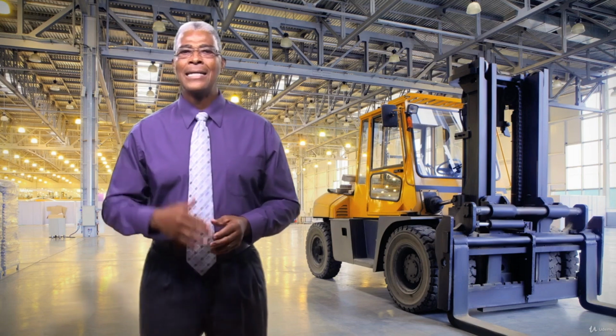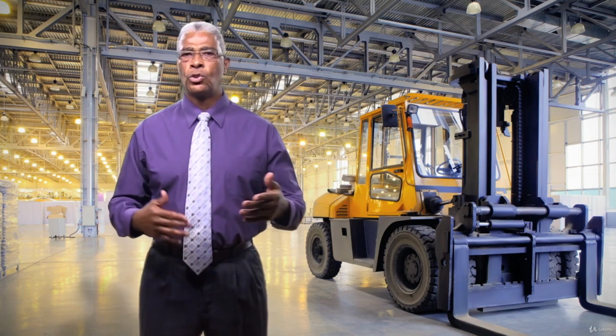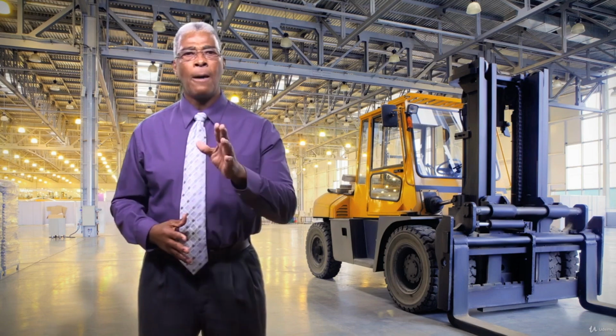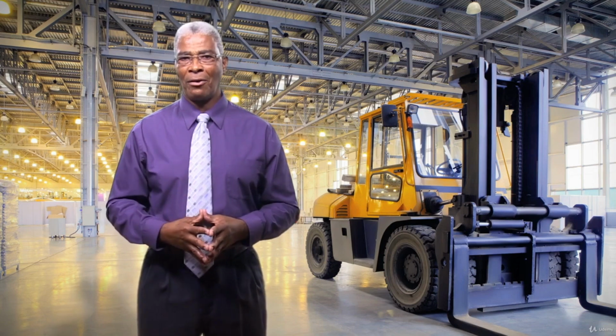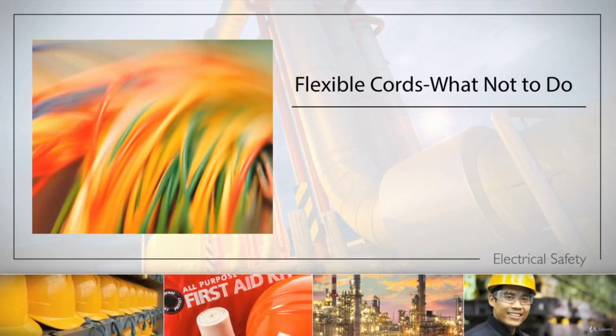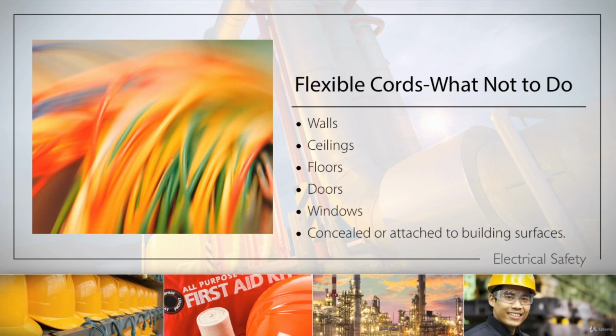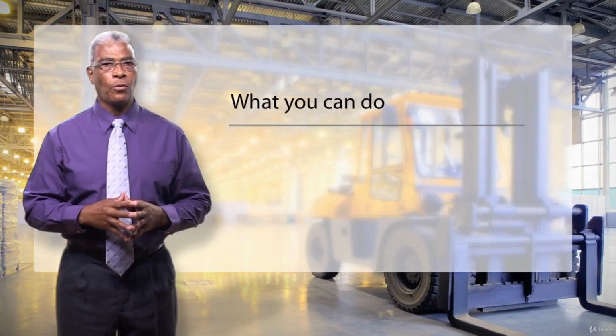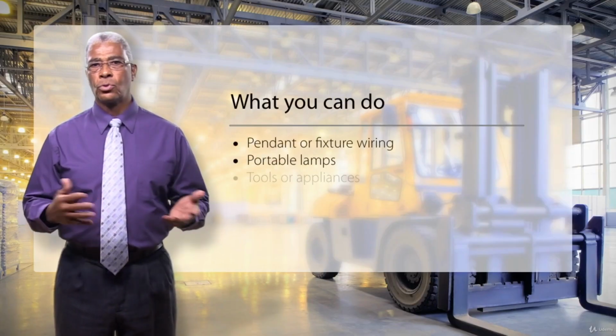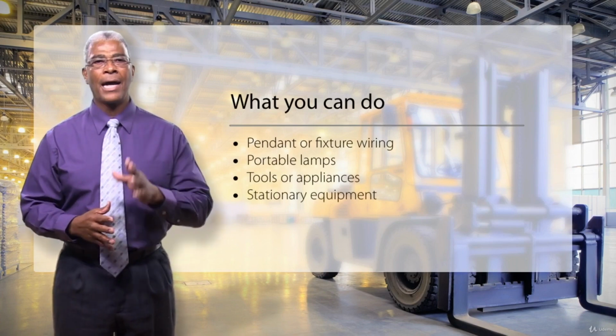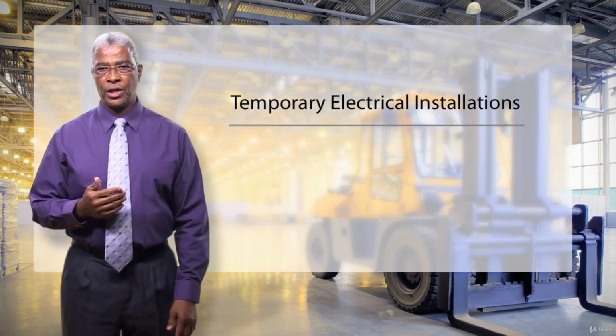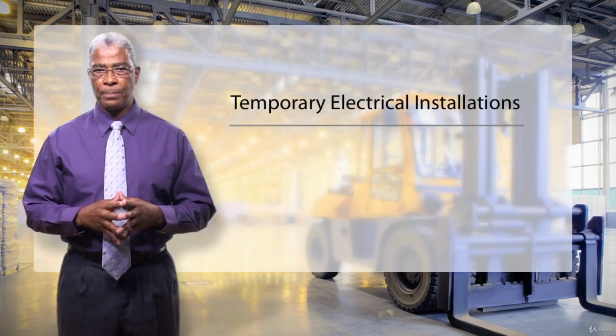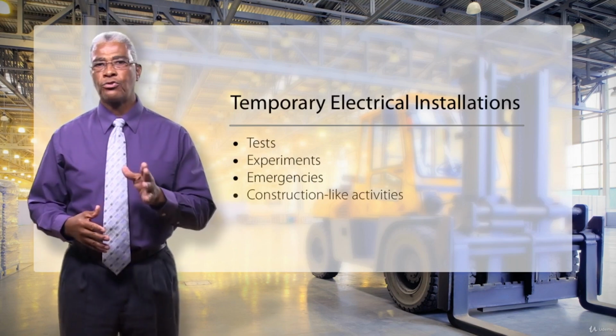Damage to flexible cords can be caused by aging, door or window edges, staples or fasteners, abrasion from adjacent materials, and activities in the area. Let's look at some examples of uses of flexible cords. Flexible cords are prohibited from acting as substitutes for fixed wiring. They must not run through walls, ceilings, floors, doors, or windows, and they must not be concealed behind or attached to building surfaces. Flexible cords can, however, be used for pendant or fixture wiring, for portable lamps, tools, or other appliances, for stationary equipment, and for temporary wiring. Temporary electrical installations of more than 600 volts may be used only during periods of tests, experiments, emergencies, or construction-like activities.